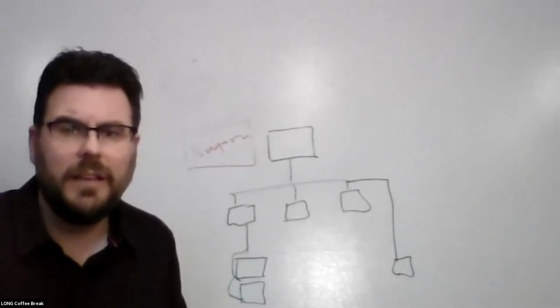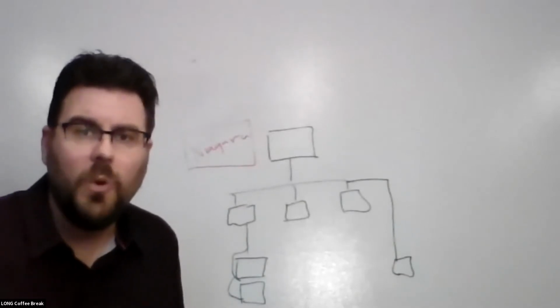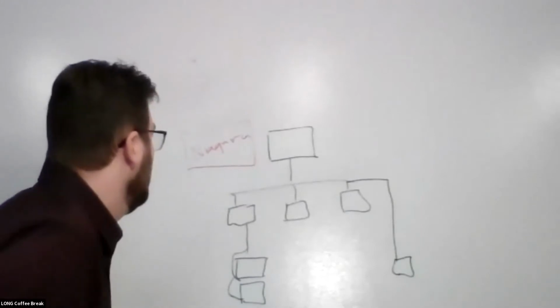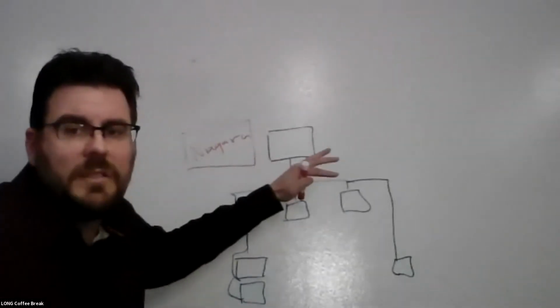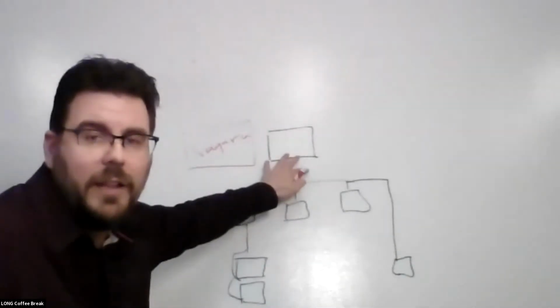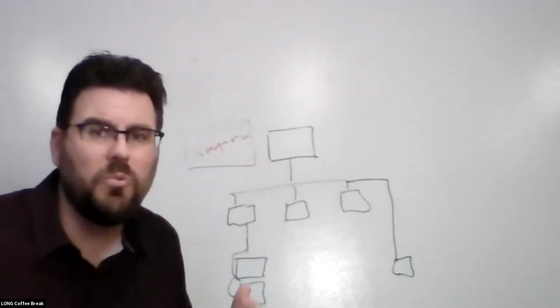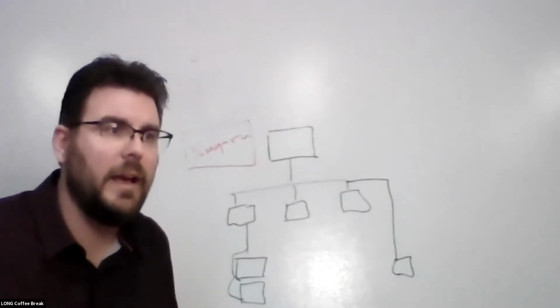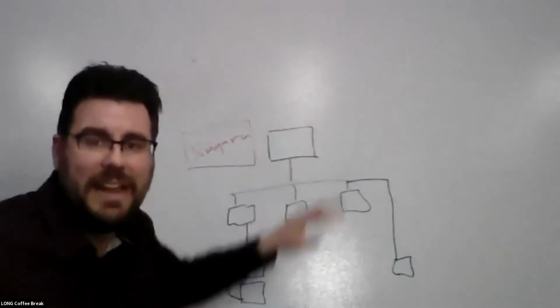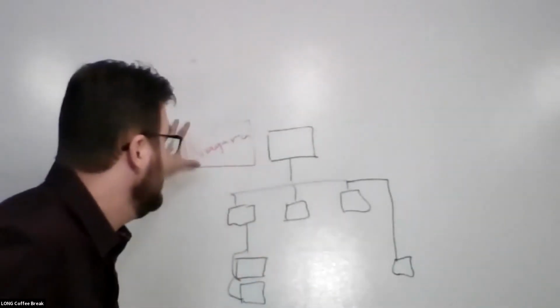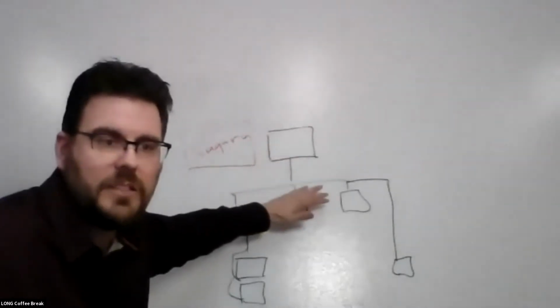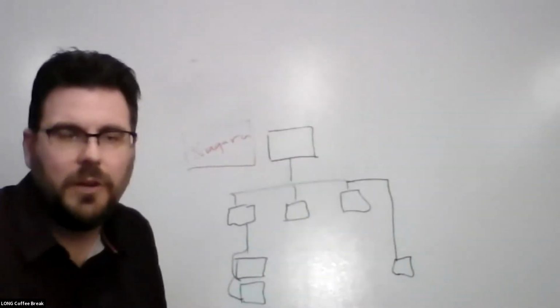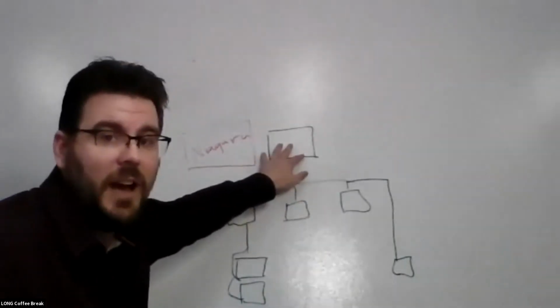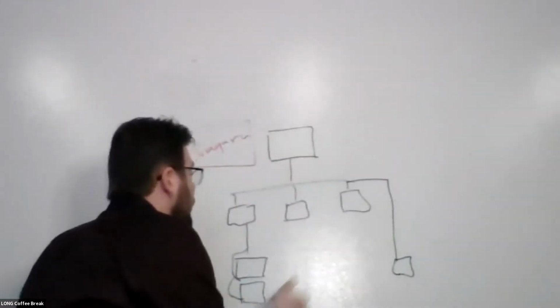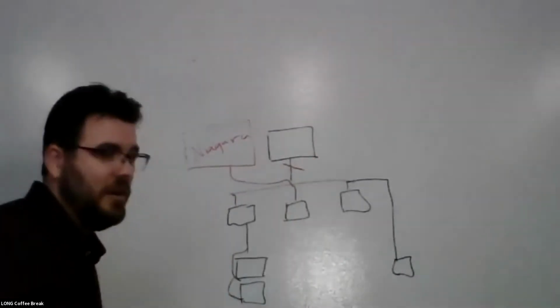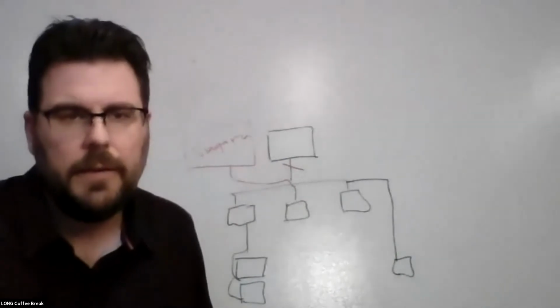So they have a server, and then they have physical hardware that can be used. The server level can be used to take over a head end. Where we typically would recommend this is if you're really unhappy with the service provider, and this head end is of an older nature, then let's go ahead and put in parallel Niagara and start to take over anything below that. Over time, you can then look at cutting this off and rerouting this whole trunk over to your Niagara server. That is one option.